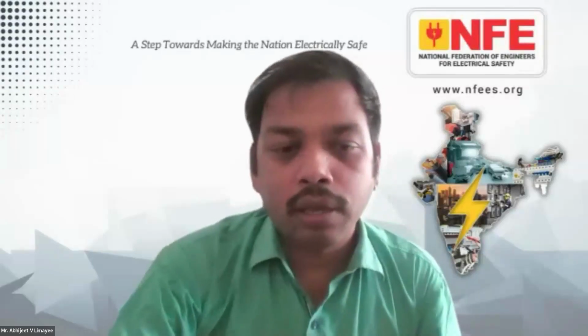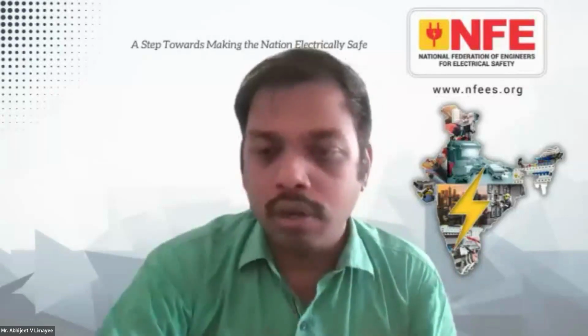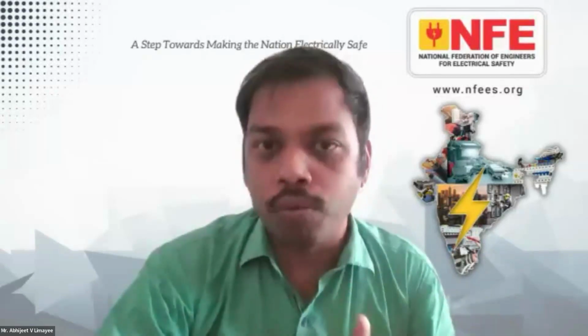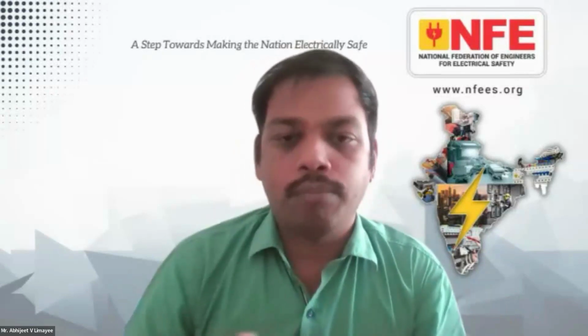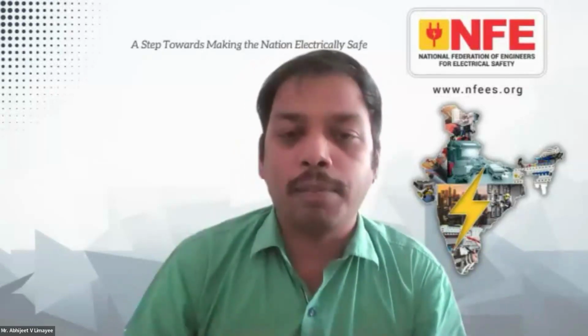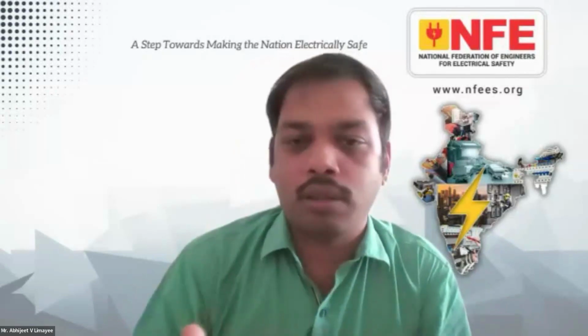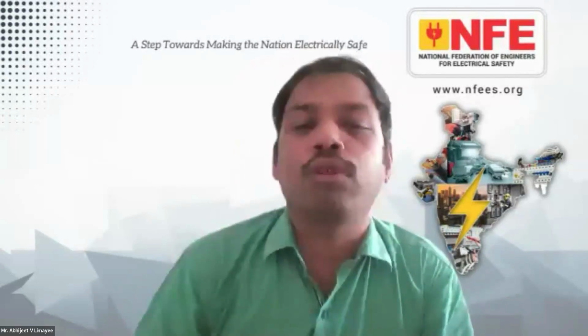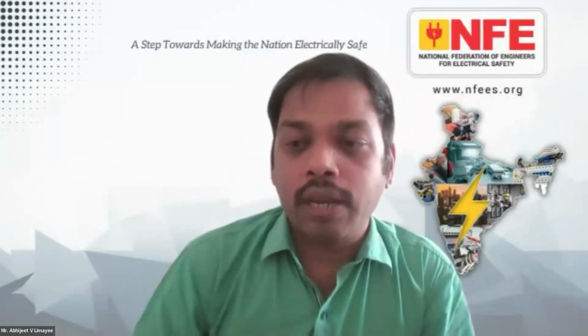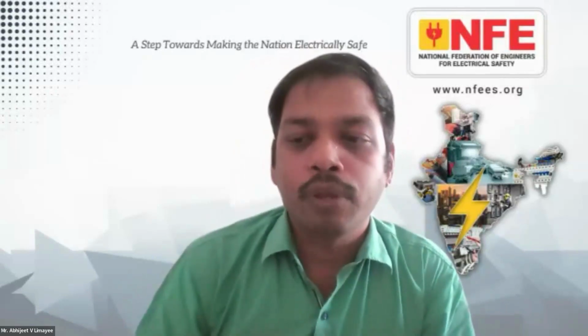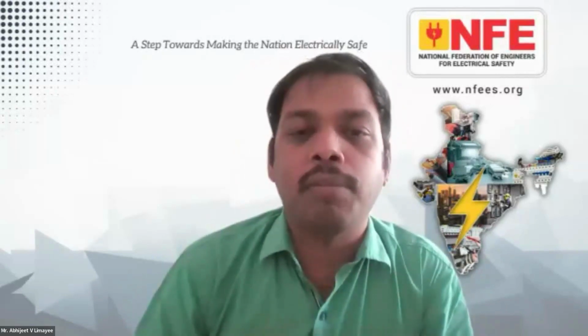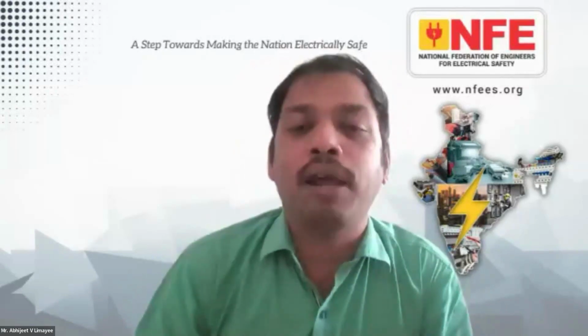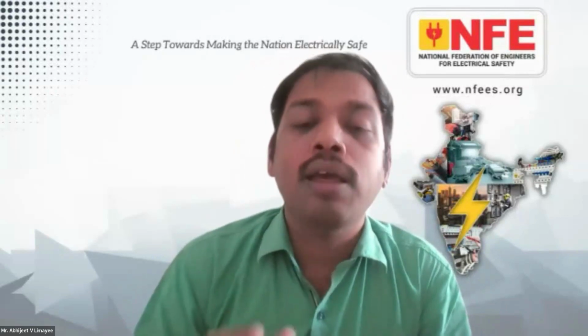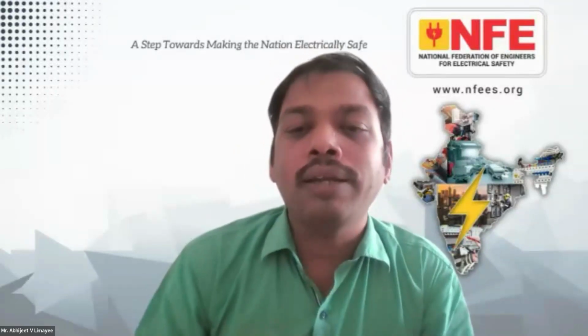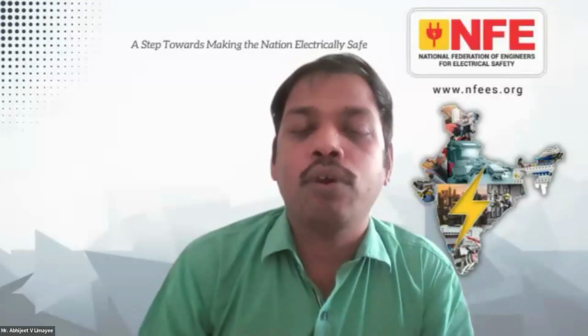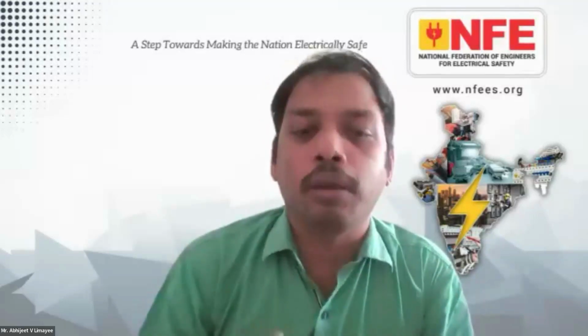See, typically when we look at this device, the test report shows it is tested as a distribution board. Now, the National Electric Code talks about IEC 61439 as the basic guiding standard for distribution enclosures, and even 60364 also specifies 61439 as an enclosure standard. Now, for any MCB distribution board that goes into a building, every manufacturer making the MCBs and distribution boards tests it as per IEC 61439 with the MCBs and the distribution boards together, so that even an ordinary operator would not face an electric shock when operating the DB.